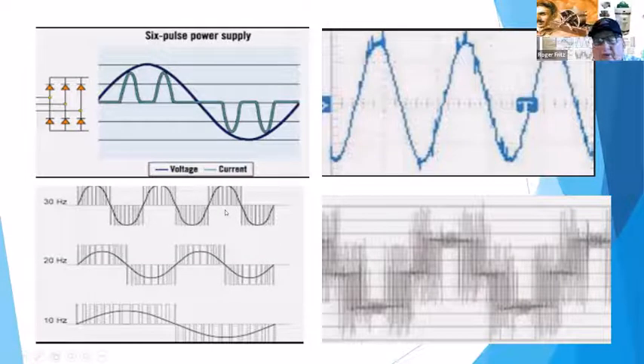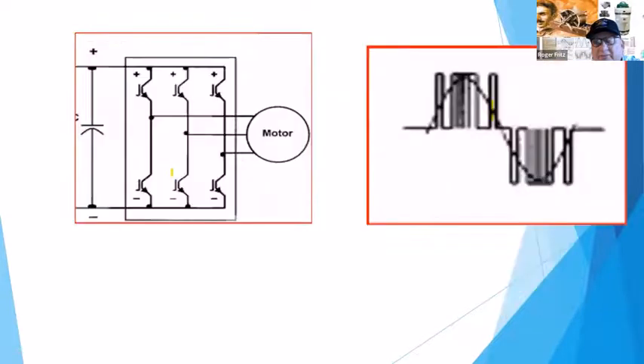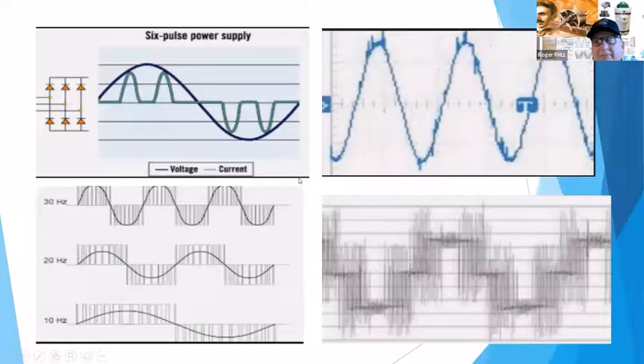So again, with the transistor output of the drives, we're basically controlling these waveforms. Instead of a fixed 60 cycle or 50 cycle power, we can regulate this power. As you can see here, we can regulate it to 30 hertz power, 20 hertz, 10 hertz. We can also go up to 40, 50, 60, all the way through the range. A lot of this is used even for high frequency. If you want to run a motor up to double its speed, all we have to do is turn it up to 120 hertz. But you have to be aware of all the mechanical restraints in your equipment when you do that.